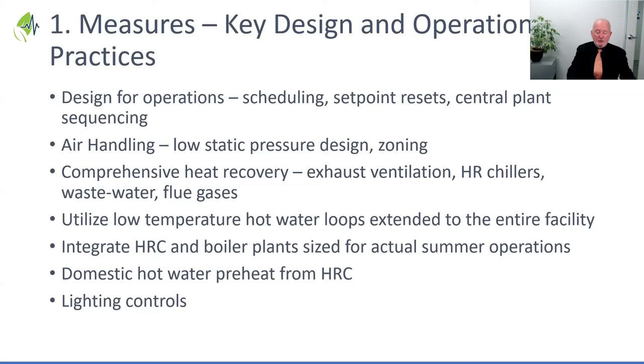So exhaust air, every exhaust air fan has its heat extracted and put back into the building - that's the heat recovery. Chillers pull out all the process loads; no air-cooled condensers running in winter, that's verboten. Wastewater leaving the building has to give up its heat before it makes it to the sewer. To the extent we're still using boilers, and for the foreseeable future we will be, we're fully recovering all the heat from the flue gas - condensing heat recovery, putting what's left of that into the heat recovery chiller.